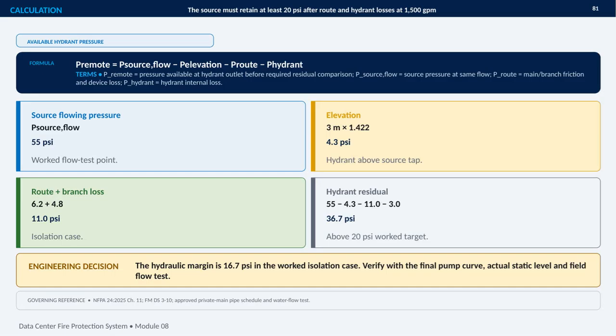This slide shows how we determine the pressure available at the remote hydrant, using the worked isolation case. The governing relationship is straightforward. Remote pressure equals source flowing pressure, minus elevation loss, route and device losses, and hydrant internal loss. The source is flowing at 55 psi. Elevation contributes 4.3 psi of loss, based on a 3-meter rise.